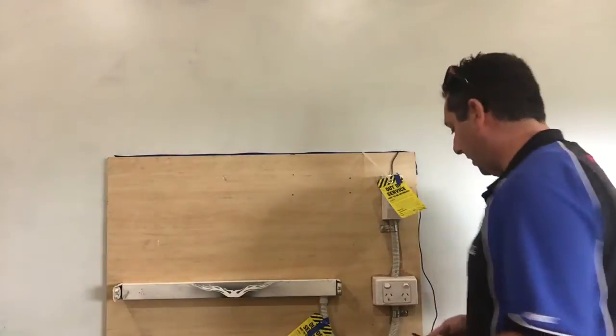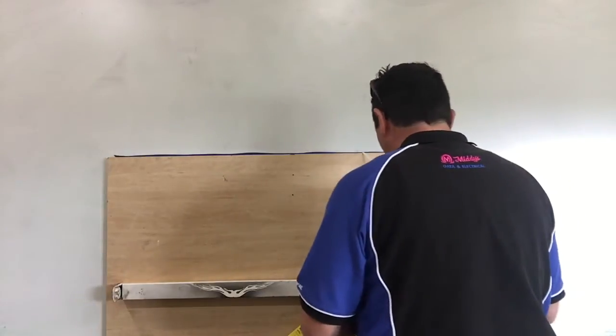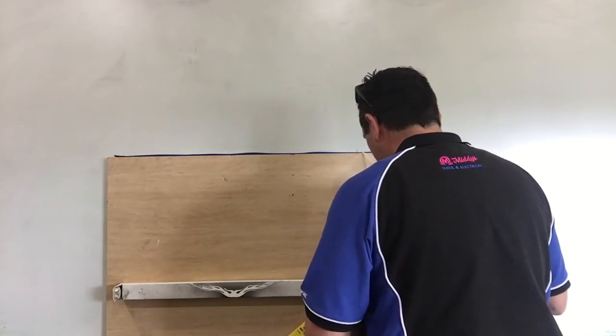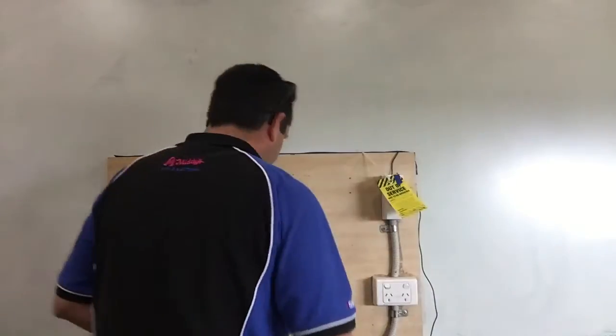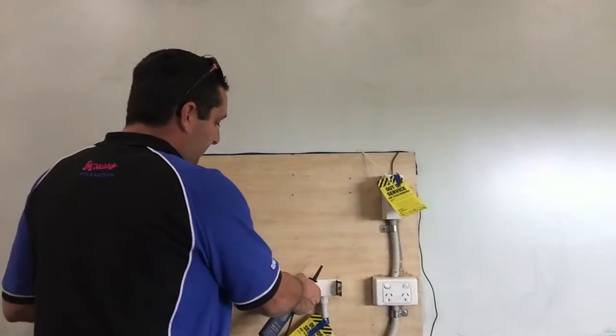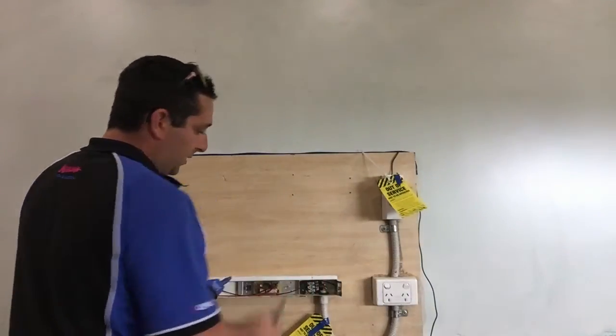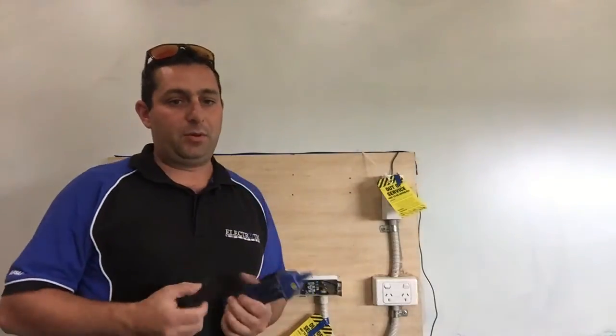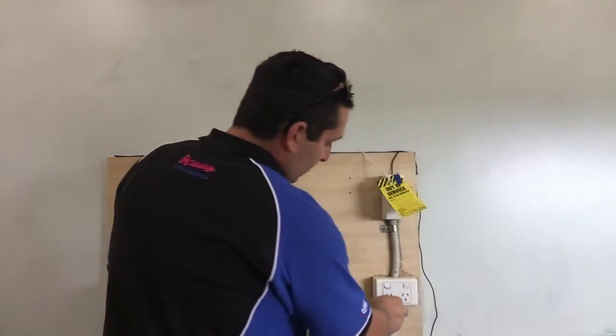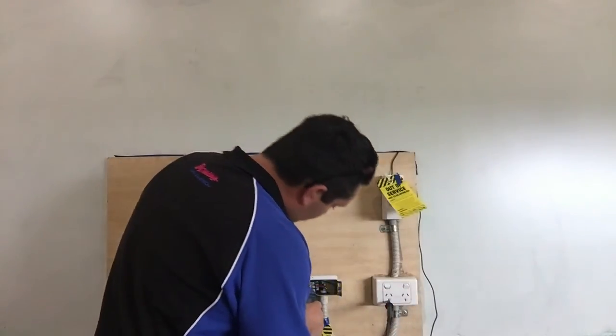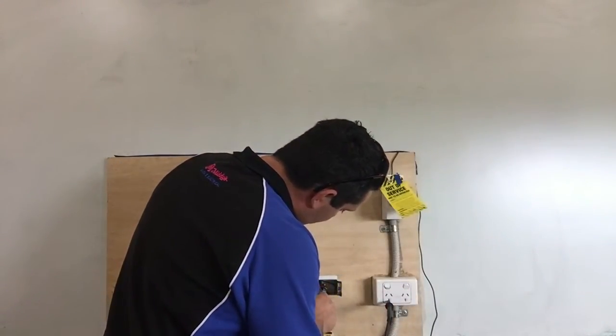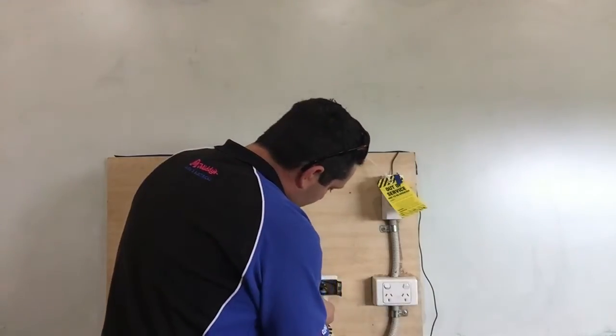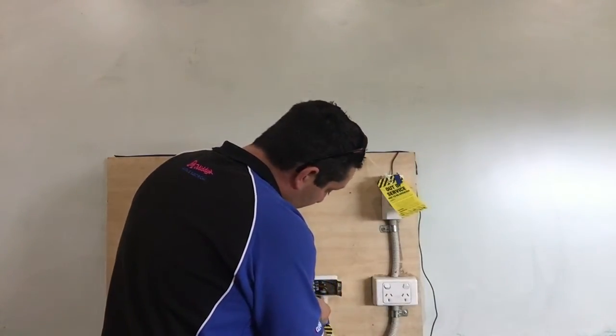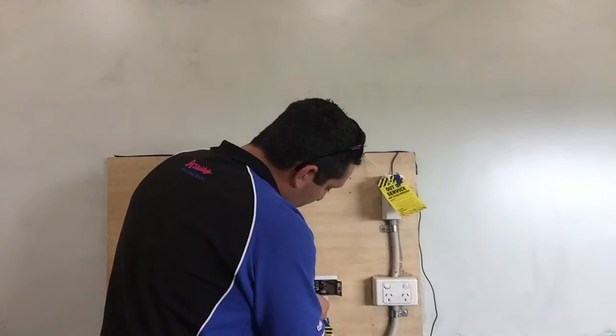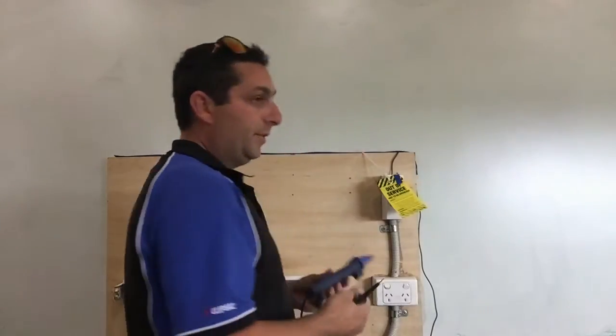So now that we're actually into the disconnection, we can test our tester, active, neutral, active earth, neutral earth. Once we've established that, we can remove the cover of our appliance, and we're going to test our appliance. To do that, we're going to do it from our earth to active, earth, neutral, and then actually between the conductors, active, neutral, active earth, neutral earth.